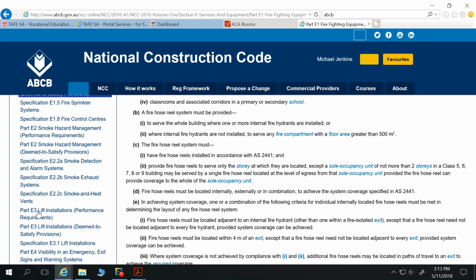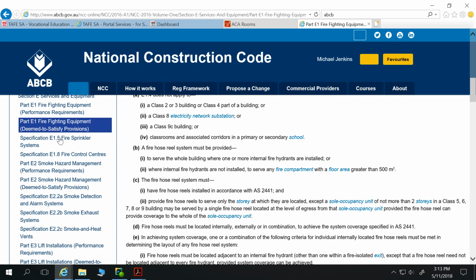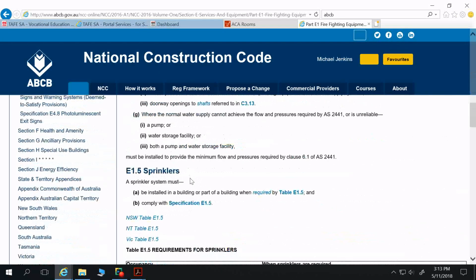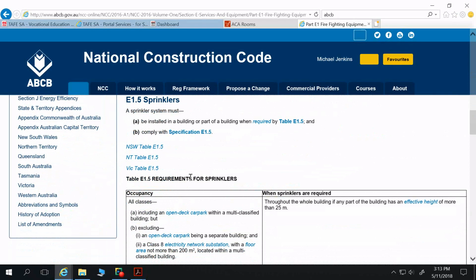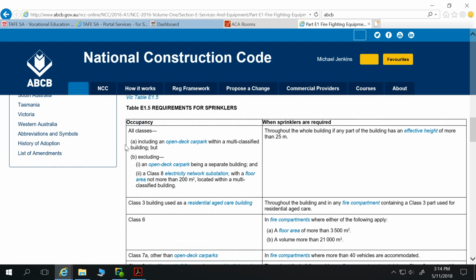Do we need a sprinkler system? So we've got sprinklers, E1.5. So that's, here we go. 1.5. Okay, sprinklers. A sprinkler system must be installed in a building or part of a building when required by table E1.5 and comply with specification E1.5. So the first thing, we have to look at table E1.5 to see if we even need a sprinkler system. So, need a sprinkler system in all classes, including open deck car park, excluding open deck car park electric network substation. So all classes throughout the whole building, if any part of the building has an effective height of 25 metres or more.